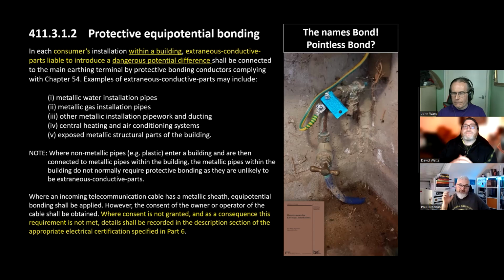But what it does do is it talks about getting consent to bond. Let's say you've got a multi-core cable coming in for telephones or whatever, and there is an exposed or extraneous part to it. We need to get consent to do something with that as far as bonding it. But it then adds, where consent is not granted, and as a consequence this requirement is not met, details need to be recorded on the certificate. And that's another thing that comes in this regulations, ensuring that we're defining more and more departures and more issues on the certification.